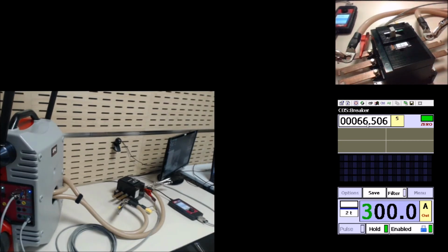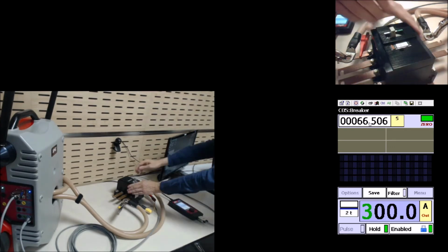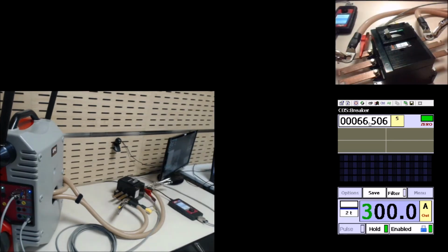So we are going to repeat this test, and you will see how this time decreases a little bit. We close the breaker again and just press on again. Remember, we got 66 seconds for the first trip, but now the breaker is warmer than it was in the first test. You see, it's now 37. So it's very close to half the time we got in the very first test.